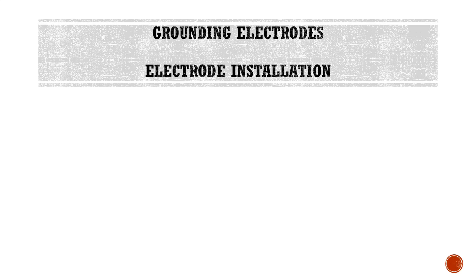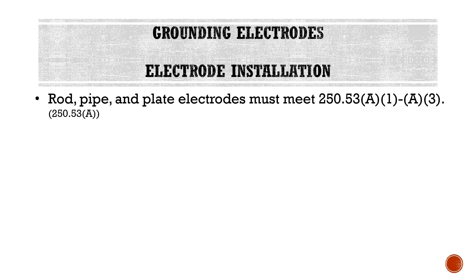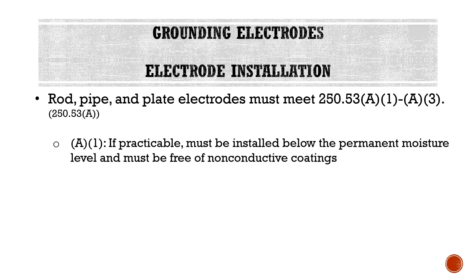Now let's talk about how to install those electrodes — applicable only to ones that we ourselves would install. Rod, pipe, and plate electrodes must meet 250.53 A1 through A3. A1: if practical, must be installed below the permanent moisture level and must be free of non-conductive coatings. The idea of the permanent moisture level is we want it installed below the freeze level — if it's below where the ground gets moist, it won't freeze in cold temperatures, which would impede conductivity to the ground around it. And we don't want any non-conductive coating because that defeats the purpose of establishing a conductive path to the Earth.